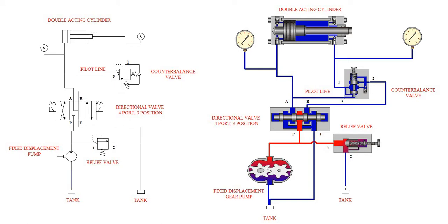Well, what is the counterbalance valve? Counterbalance valves' jobs are to manage pressures and flows coming from overrunning loads. So what you have to envision, and it's not depicted here, is something trying to pull this cylinder out, make it extend, some kind of a load on the rod. Maybe if it was mounted a certain way, it could be a gravitational type load depending on how it's oriented. But we don't want this cylinder to run away from us when we're extending it, okay?